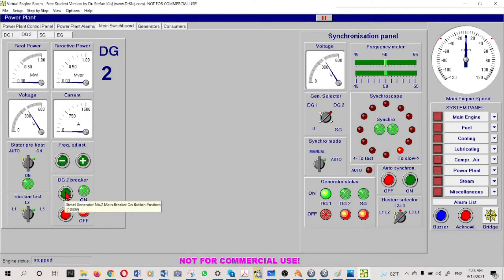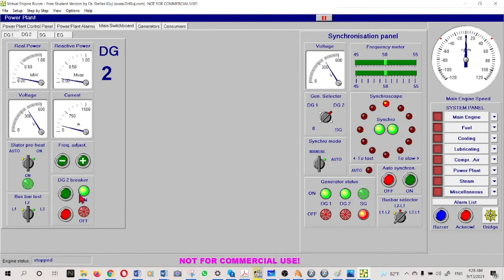Now it's okay - it's having clockwise movement. Remember I said at the 11 o'clock position we have to switch on the breaker. Now we are waiting... okay, this time I missed it. Next time at the 11 o'clock position I have to switch on this one. The generator is now connected to the bus bar.